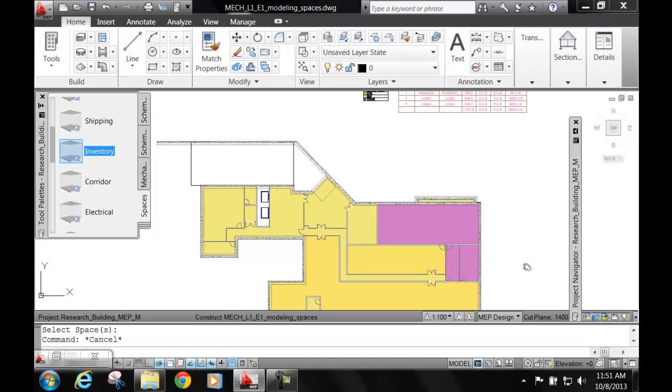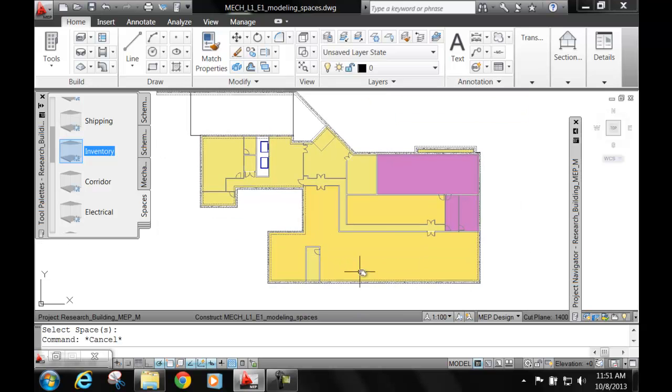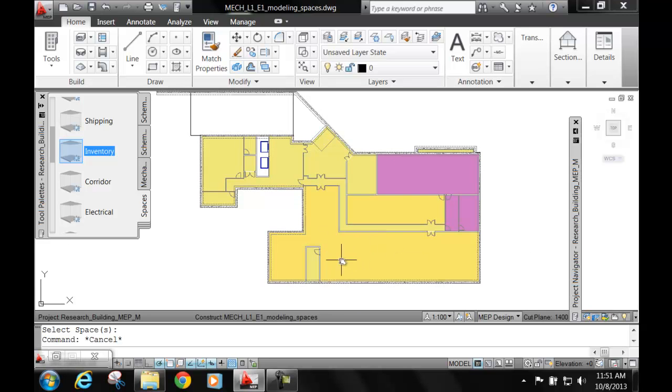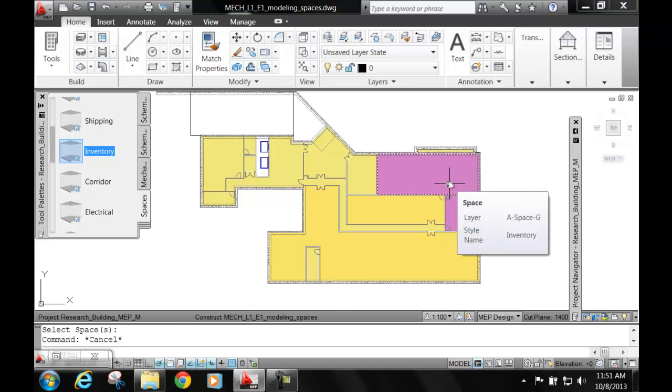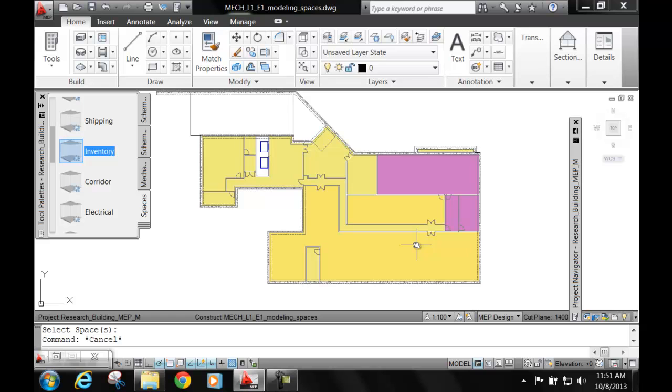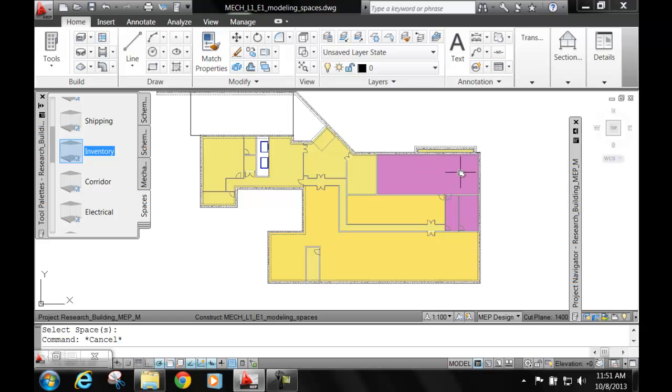Why do we want to separate the zones? This zone probably is going to have the doors open and close more. It probably faces south. This area faces north. Probably there's not as much circulation. So you want to air condition these areas differently to save energy. Your ducts are going to come from the same central unit, but you're going to have a variable air volume system that air conditions your inventory area different than your lobby area.